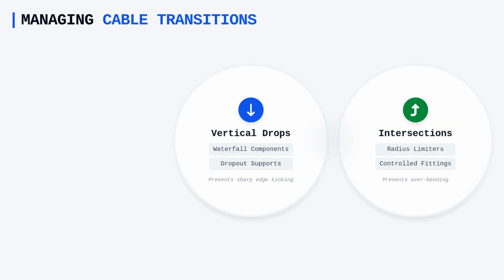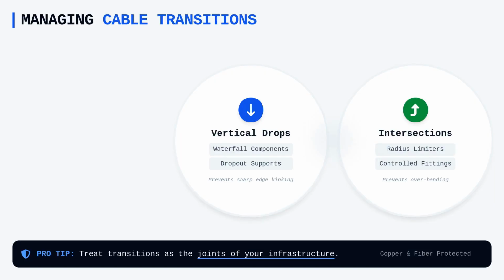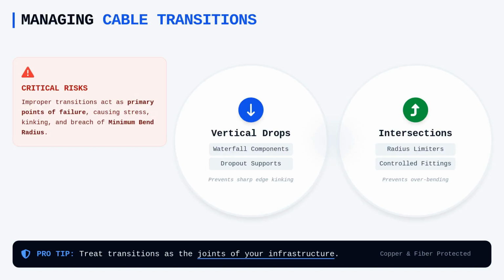Radius limiters are equally essential at horizontal intersections to prevent the cable from catching or bending beyond its rated limit. Think of these transitions as the joints in the cabling infrastructure. If they are improperly designed, they become the primary points of failure for the entire system. By standardizing the use of radius-controlled fittings, you guarantee that even the most dense horizontal distribution remains compliant with TIA standards throughout the life cycle of the facility.